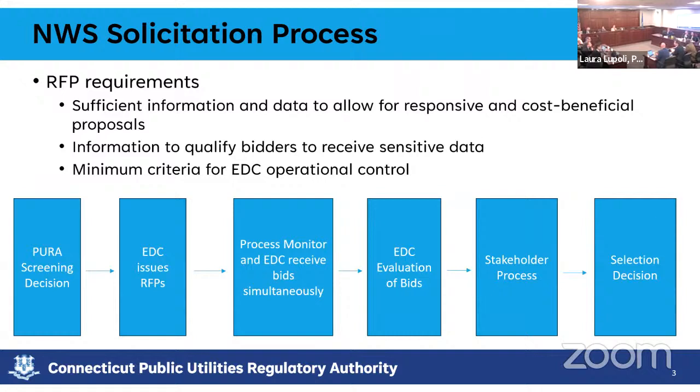Yeah, so you're referring to, even in the case of a localized solution through the non-wire solutions process, the N-1 planning standard, yes. But just to be clear, on the distribution system, we don't plan for N-1. On the substation system, we do. So if there's a substation failure, customers should not lose power because it's designed for N-1.